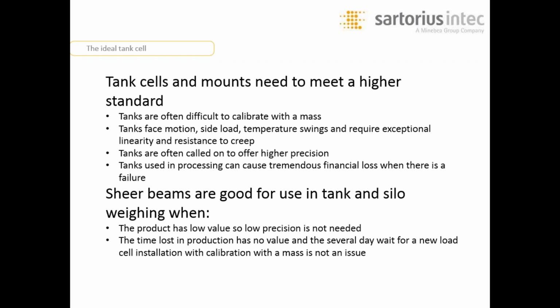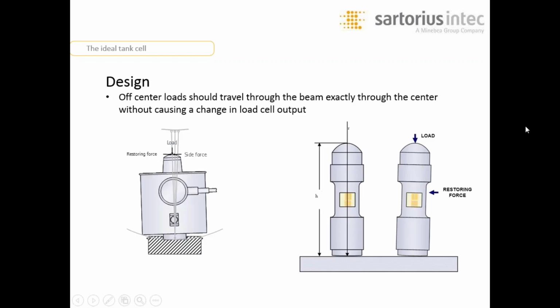Shear beams are good for use in tanks and silos when the product has low value and precision is not necessarily a big deal to the customer. The time lost in production has no value, and potentially you have to wait for a new load cell and then do the calibration of that new mass. If you have the time and the product is not terribly valuable, then load cells, or the shear beam load cell, is perfect for this application.